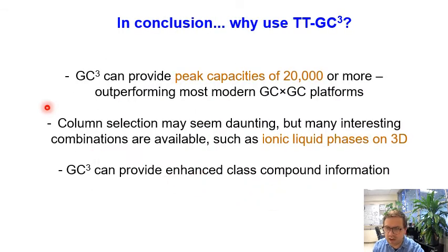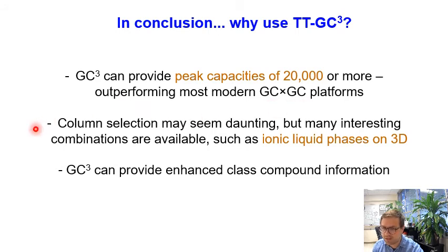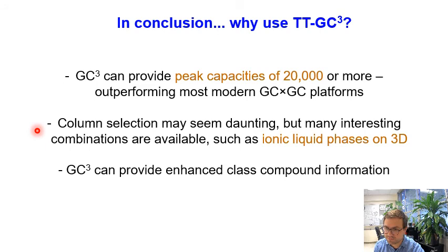In conclusion, GC Cubed can provide peak capacities of 20,000 or more, which outperforms most, if not all, modern GC×GC platforms. You might think that picking a column to use for each of the three columns may be a difficult choice to make. However, many interesting combinations are available now, such as using an ionic liquid phase on the third dimension, as shown here. Lastly, GC Cubed can provide enhanced compound class information, in particular if a better separation of one group of compounds is achieved on that third dimension separation column.